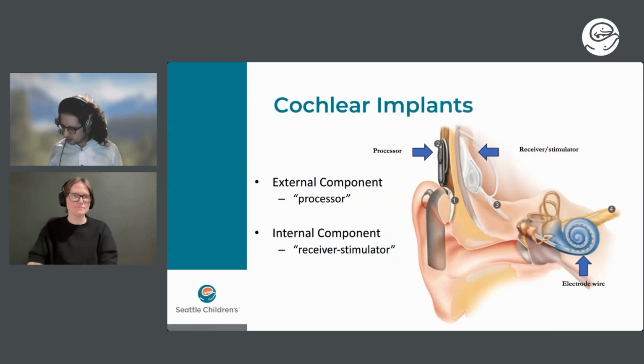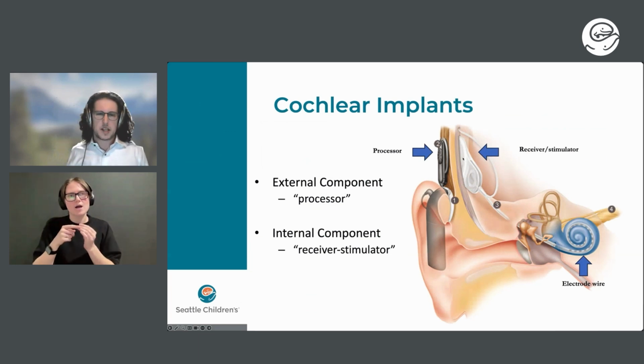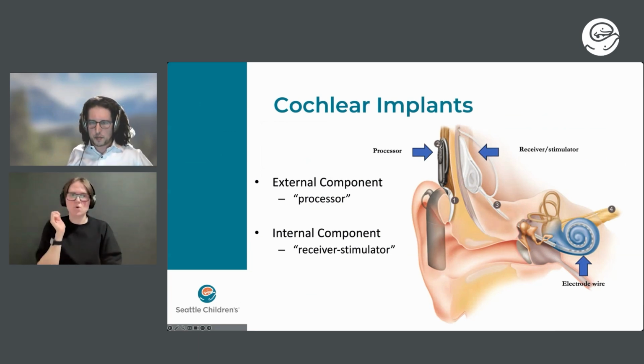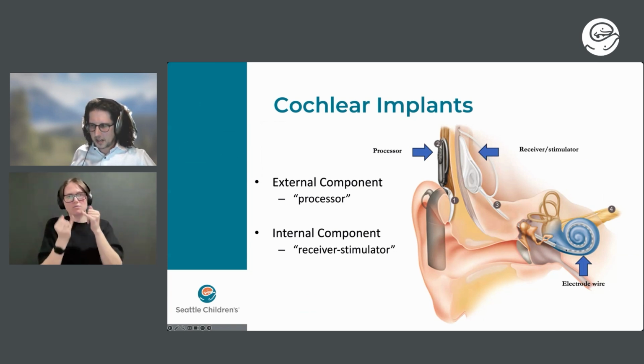So now we'll talk a bit about cochlear implants, just checking my time. Cochlear implants are all systems that have two basic elements. There's a processor that's worn externally, and then there's a receiver stimulator that is implanted underneath the skin and soft tissue against the bone. The receiver stimulator has a wire that connects to electrodes that are surgically placed into the inner ear, into the cochlea, through a small opening that we make surgically.